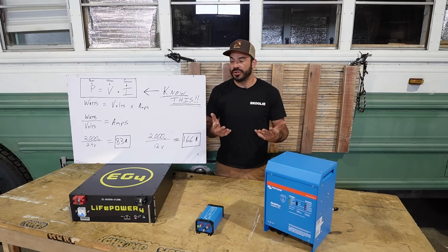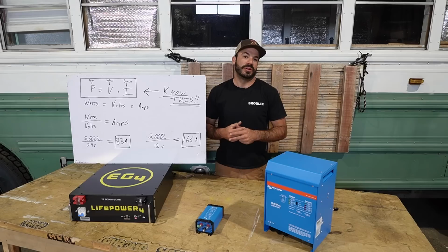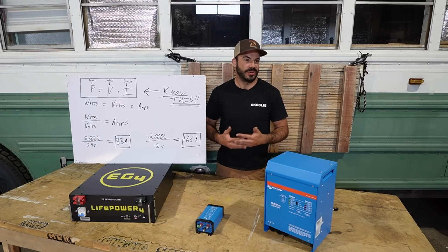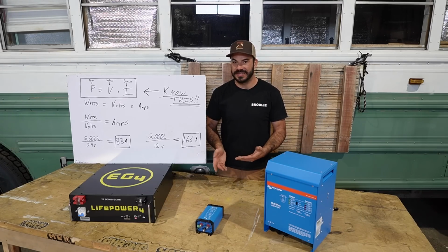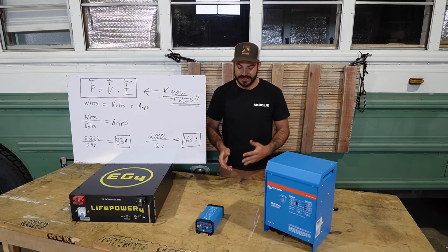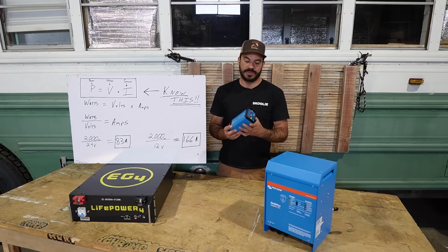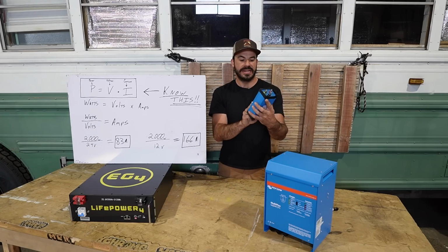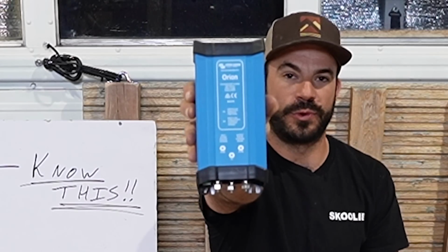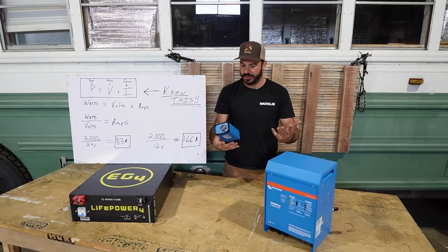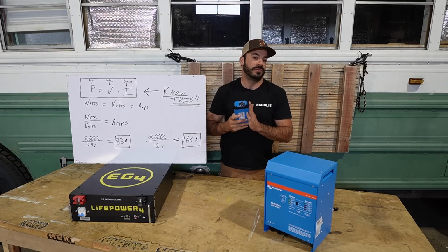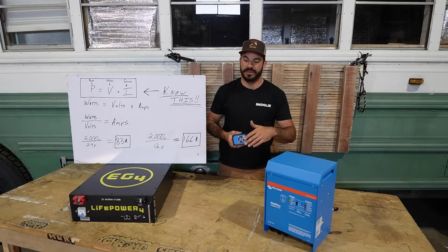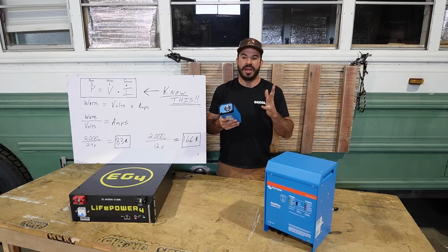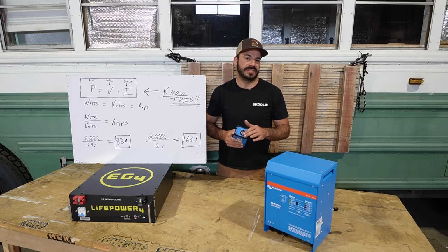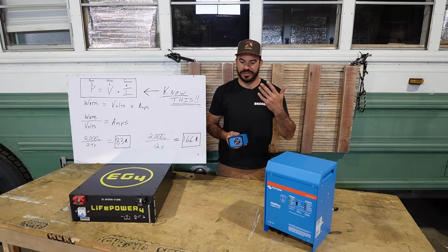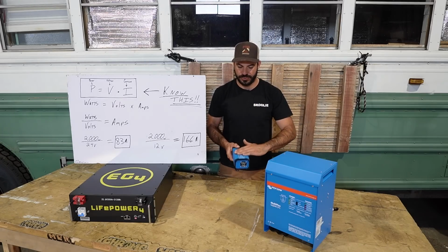Now, it's true a lot of the loads in these buses and off-grid rigs are 12 volt DC loads. So how do we power those now that our batteries are at 24 volts? The answer is a step-down converter like this one, made by Victron. It's an Orion 70 amp 24 to 12 volt step-down converter. It's a great unit—70 amps at 12 volts is more than enough power for the vast majority of rigs, unless you have a really high 12 volt DC load, like a rooftop air conditioner that's a 12 volt model, in which case you might need a second one.